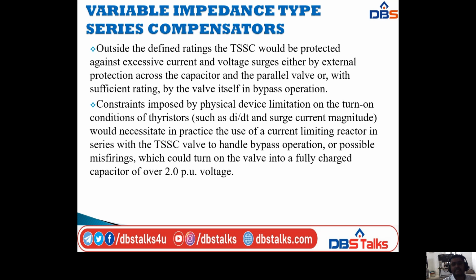Constraints imposed by physical device limitations and the conditions of the thyristor, such as the rate of change of current, dI by dt, and surge current magnitude, would necessitate in practice the use of a current limiting reactor in series with the TSSC valve to handle bypass operation. So here I am taking the current limiting reactor in series with the TSSC. This will handle the bypass operation or possible misfirings which would turn on the valve into a fully charged capacitor of over 2 per unit voltage.